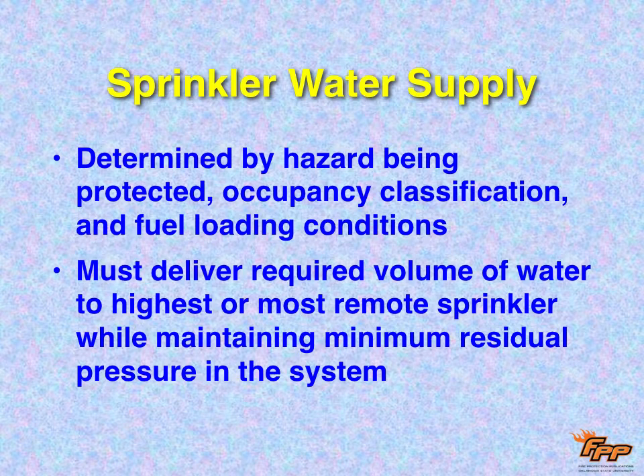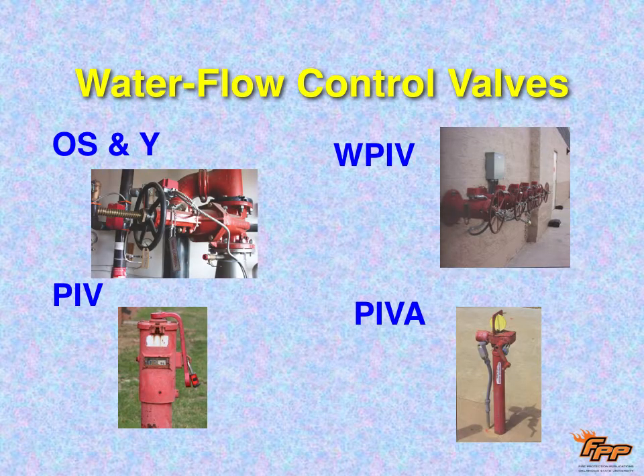It's got to be figured out so that the most remote sprinkler, the one all the way at the end of the building, has adequate pressure and adequate gallons per minute to do its job. I mentioned the valves. Some of our indicating types of valves are OS&Y, an outside screw and yoke. Top left, you can see when the screw is out, that means that the valve is open. Post-indicator valves, like the bottom left, have a little window, and in the window it says open or shut. You can also control the water flow by turning this off or on with this device, but it also tells you whether it's on or off.